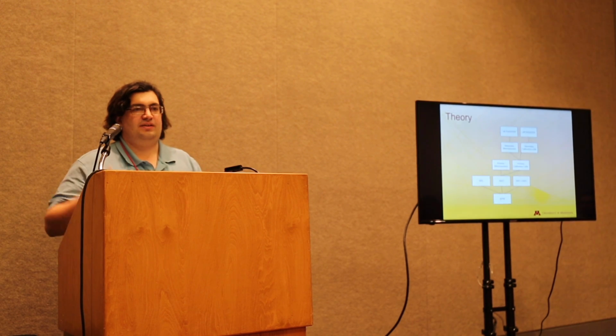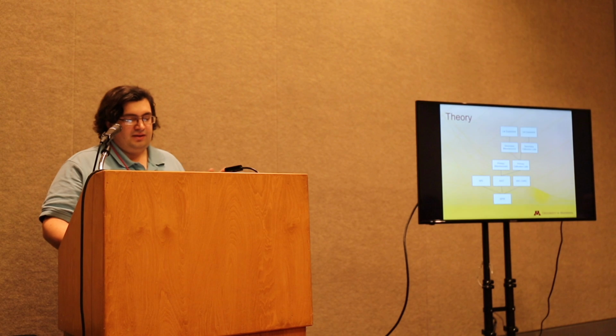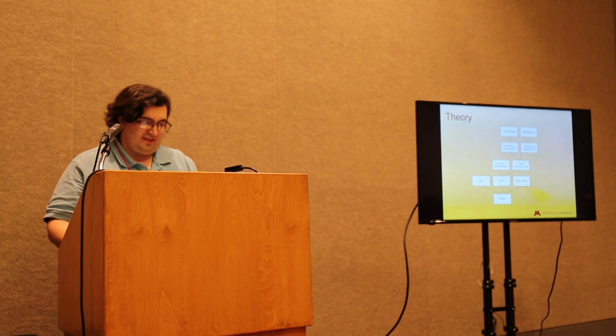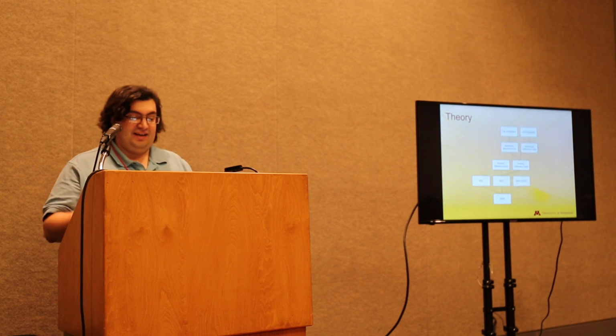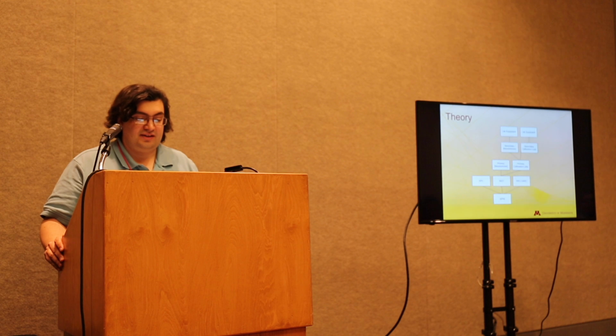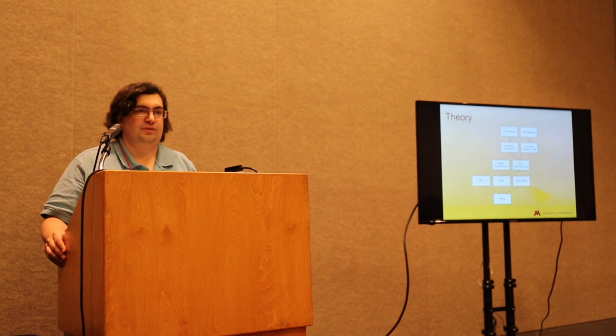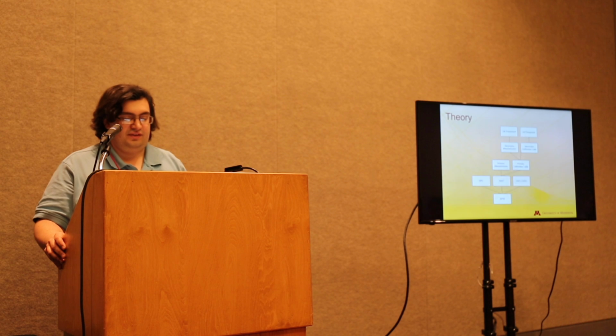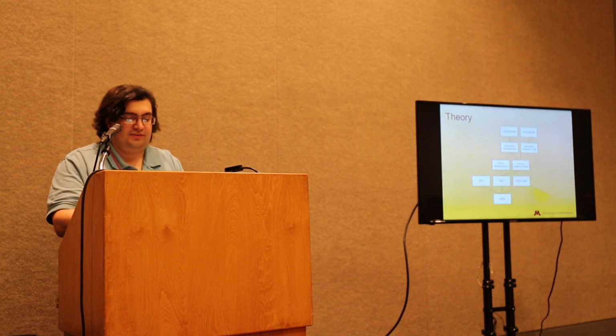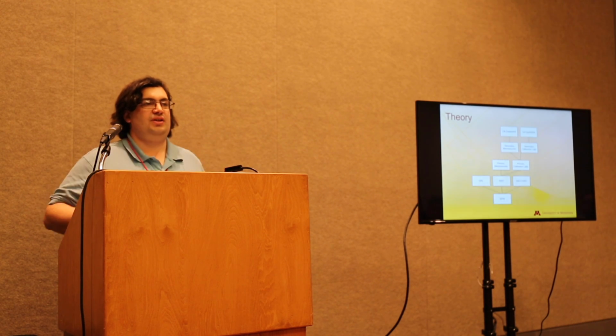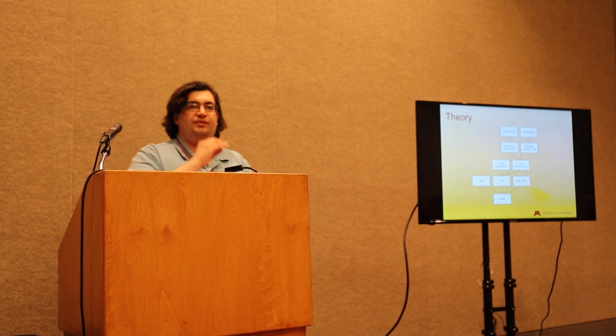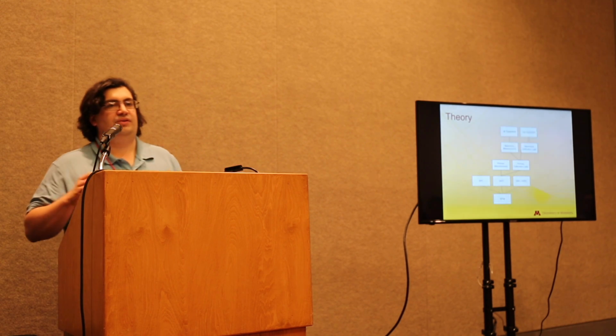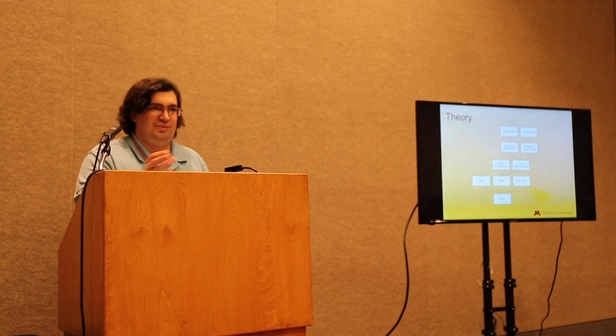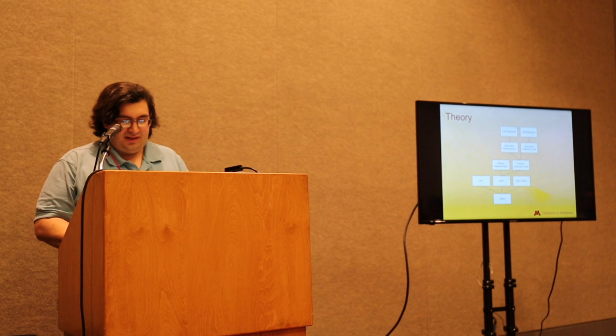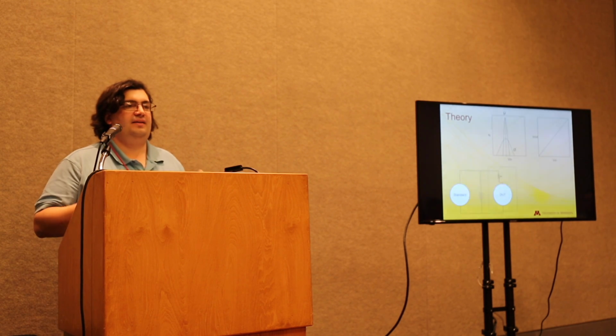How uncertain we are traces back to the measurements that we use. The basic measurements come from the Bureau International des Poids et Mesures, I believe I'm pronouncing that very badly, in France, just outside Versailles, where they have international standards. Then you have next generation standards laboratories like the National Physical Laboratory in the UK, or NIST, the National Institute of Standards and Technology here in the US, or NRC, CNRC in Canada. And then that goes to primary manufacturers and their primary calibration labs. And what happens is generation after generation you establish a chain of traceability, very low uncertainty measurements created by standards against which things that you build can be compared to know that a volt truly is a volt, plus or minus some number of very, very small microvolts.